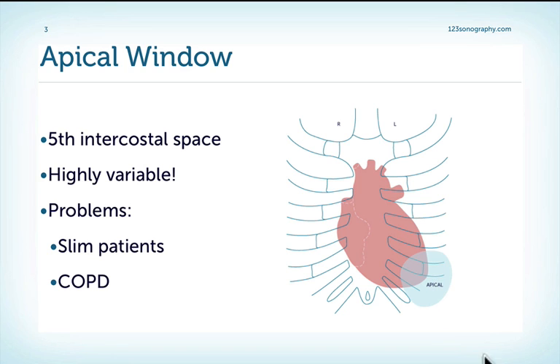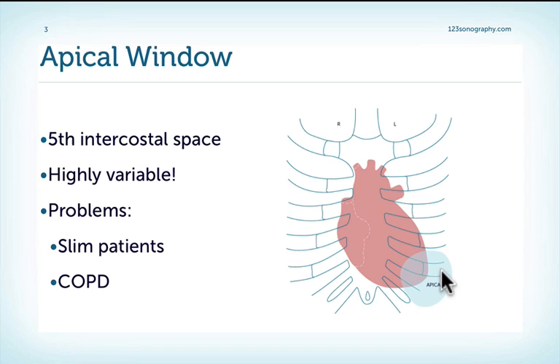Where is the window located? It's located at the apex, which can be very variable. Usually it's somewhere in the region of the 5th intercostal space, but it can be located further up or sometimes even further down, and the apex can also be rotated more towards the back or even more towards the sternum. So there's a high variation, and you will have to just play around with the transducer until you find where the apex is.